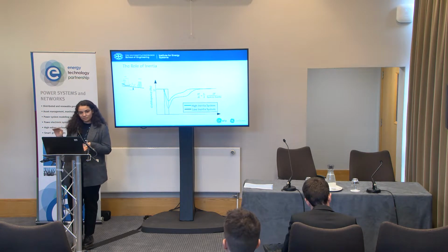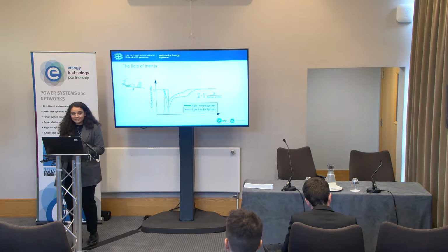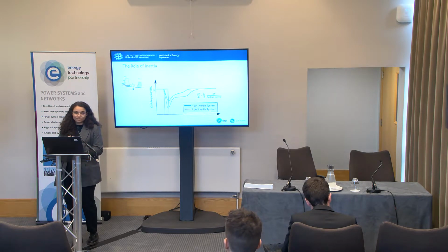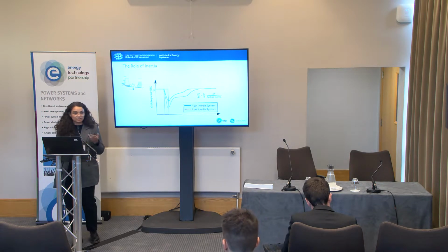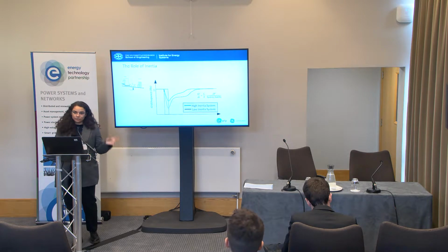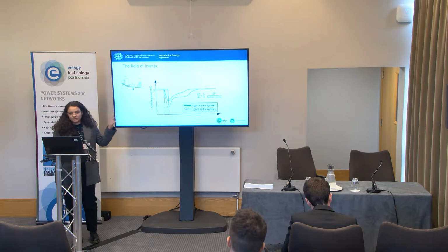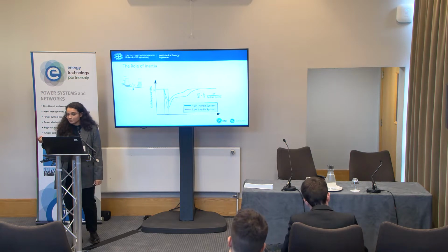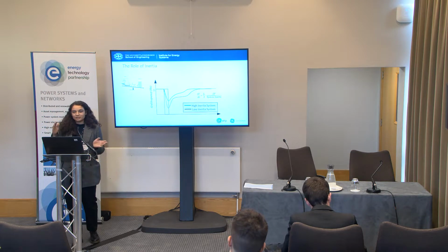Generators are where we get most of our inertia, and the generators with the most inertia are gas and coal and nuclear. The generators with no inertia or limited inertia are solar, wind, and other types of renewables. So as we add more renewables to the system, this becomes a bigger problem. And we're at the point now where quite often in the UK, the connected inertia at any given moment is below the threshold that National Grid consider acceptable.